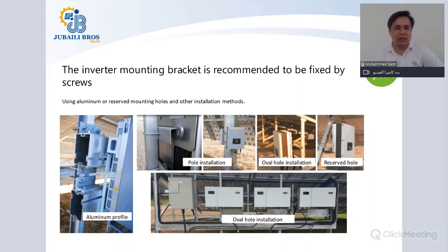Going ahead with the presentation, the inverter mounting bracket is recommended to be fixed by screws. All Huawei inverters come with a frame inside the inverter packaging, which you can put onto the wall, and then you can hang the inverter on it. After hanging the inverter onto that bracket, you must screw the inverter to that bracket as well. You can also fabricate customized brackets for the inverter, such as for a pole installation, or for oval hole or reserved hole installation scenarios.